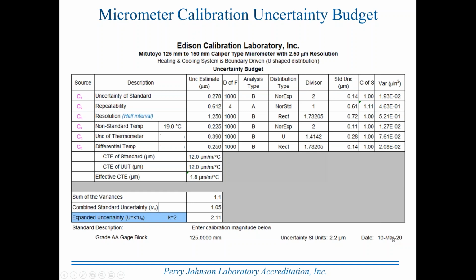And you can have the spreadsheet set up so it records the date when the calibration was performed. Here we put in some additional information. We've identified the standard. You'll see C1, C2, all the way through C6. These are contributors, contributor 1, contributor 2. We've identified them a little bit here. We make note that the resolution is based on the half interval so that you don't forget which one you used. We enter the coefficient of thermal expansion of the standard and the coefficient of thermal expansion of the unit under test, and it calculates the effective coefficient of thermal expansion.